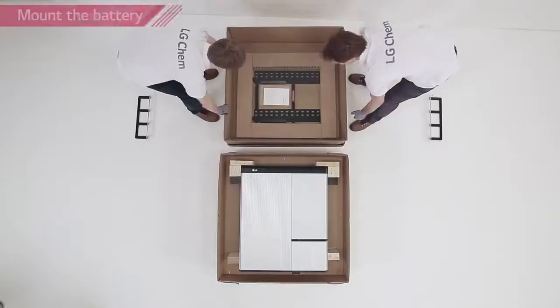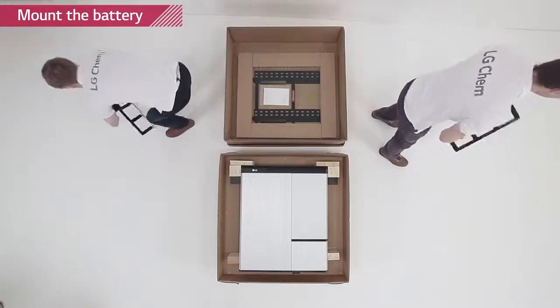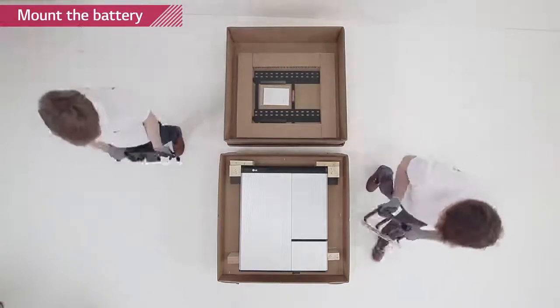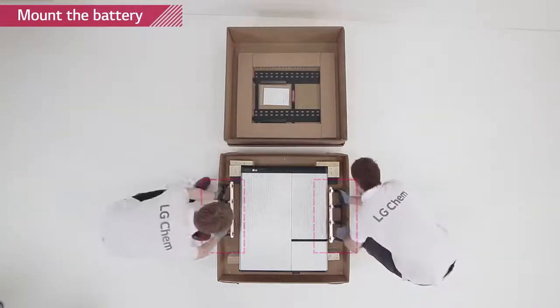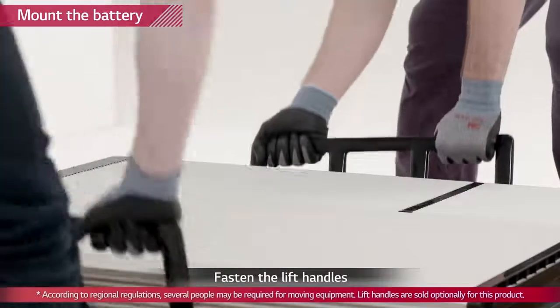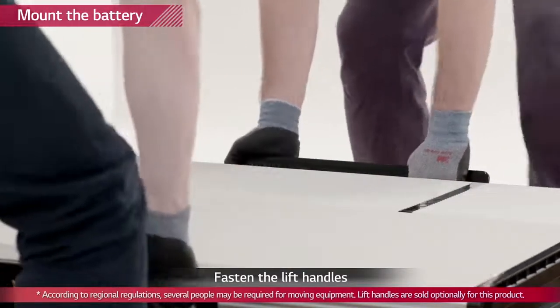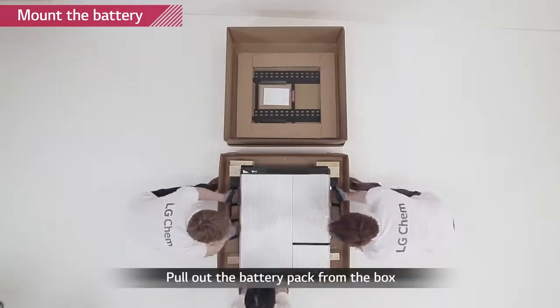Attach the lifting handles to the hex socket screws located at the back of both sides of the RESU pack. Lift the battery pack using the handles. Handle the RESU10H carefully as it weighs about 100 kg. Note that the wall on which the battery pack will be mounted must have a capability to support weight over 150 kg.